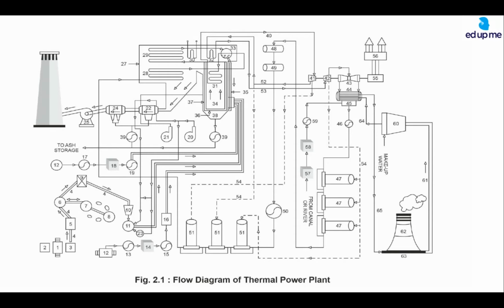So it is crushed to a very small size, which can be handled by the coal mill. From the coal, the boiler house bunker, the coal goes to the coal mill, that is number 11. From 11, the coal is completely milled. Milled means it is pulverized. Pulverizing is 200 BS mesh, very small. It is in powder form.